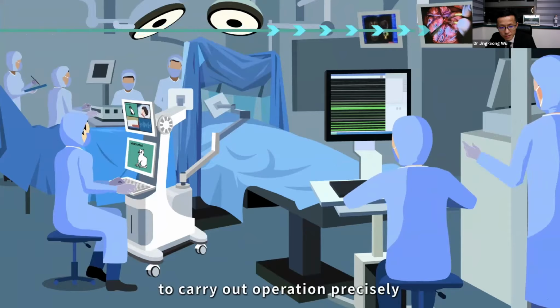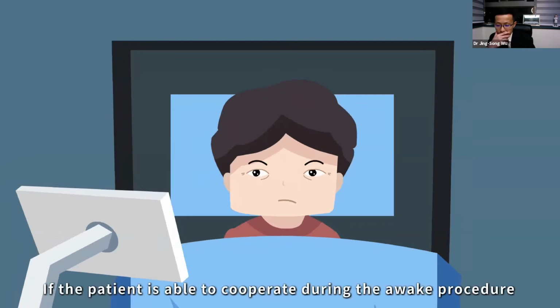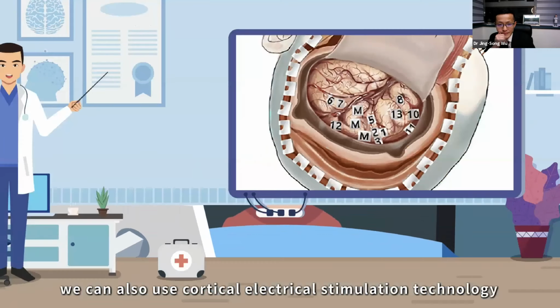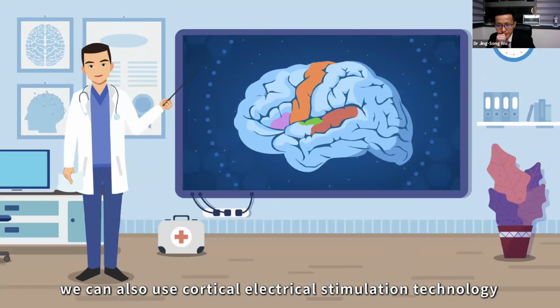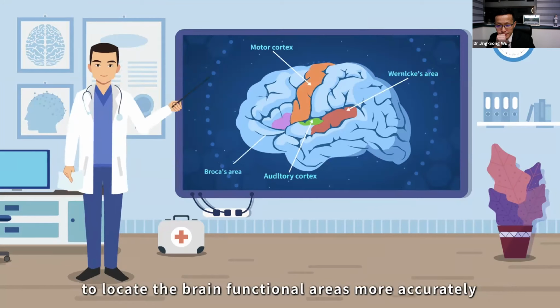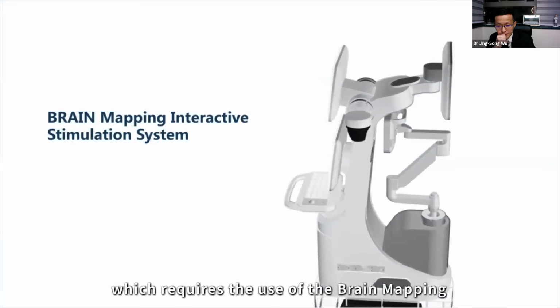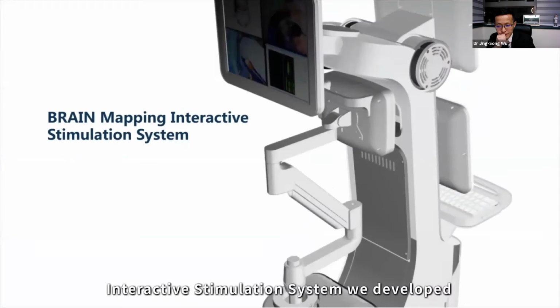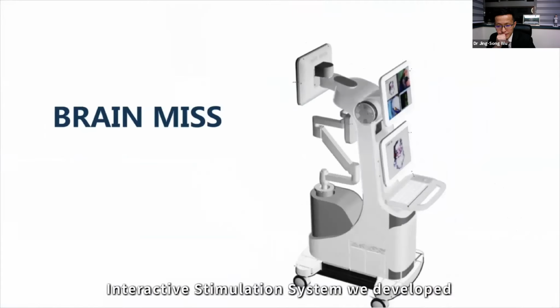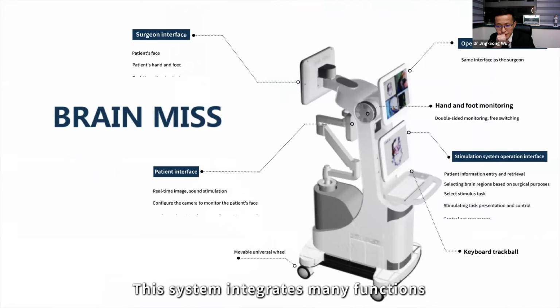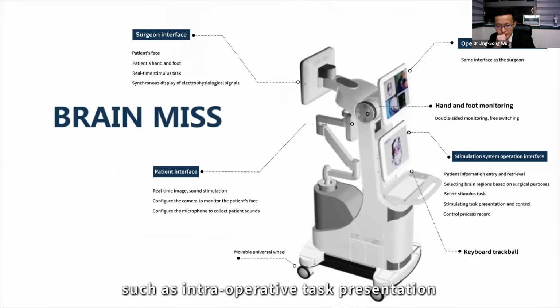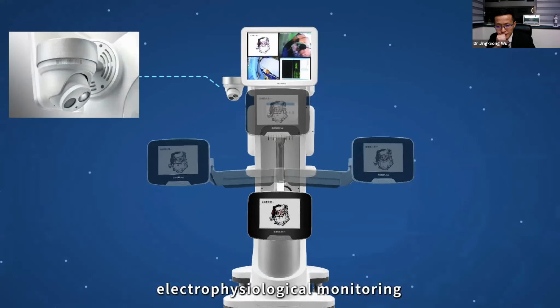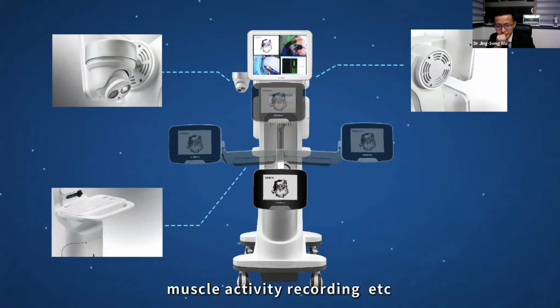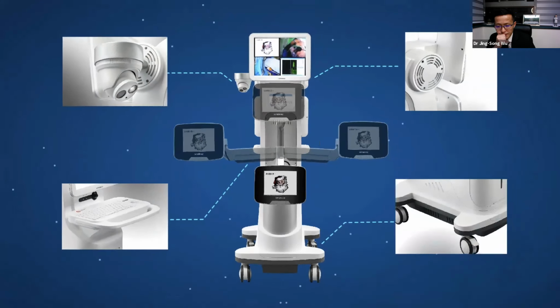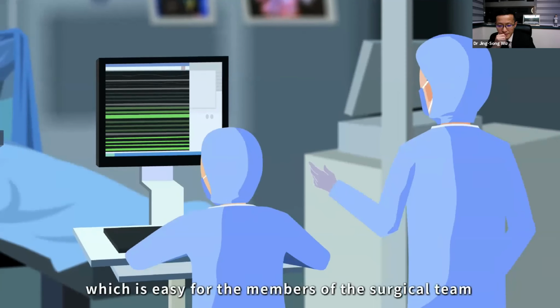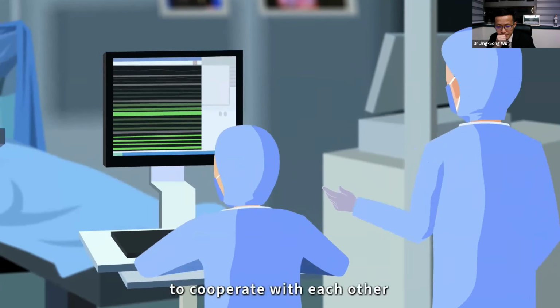If the patient is able to cooperate during the awake procedure, we can also use cortical electrical stimulation technology to locate the brain functional areas more accurately, which requires the use of the brain mapping interactive stimulation system we developed. This system integrates many functions, such as intraoperative task presentation, electrophysiological monitoring, muscle activity recording, etc., which is easy for members of the surgical team to cooperate with each other.